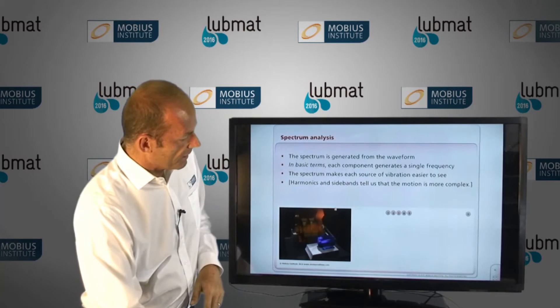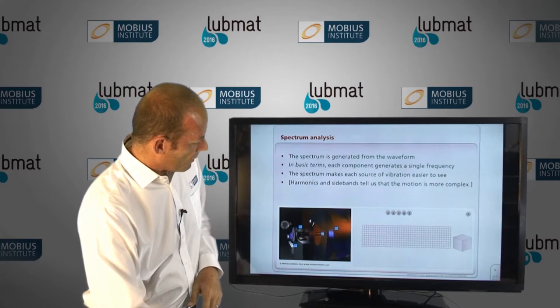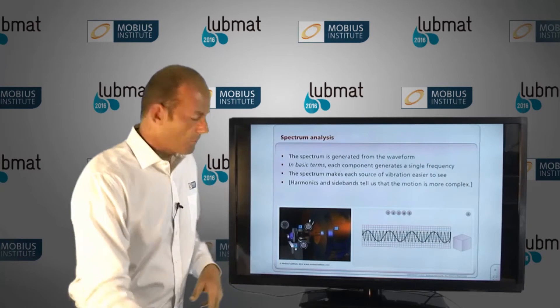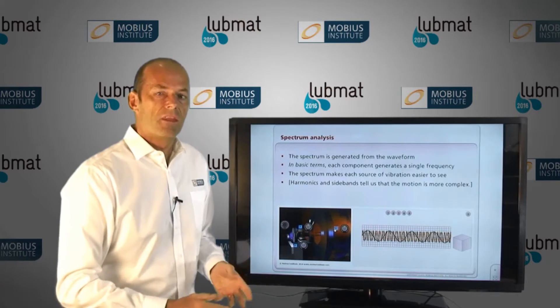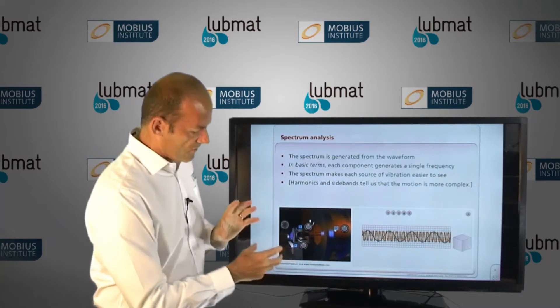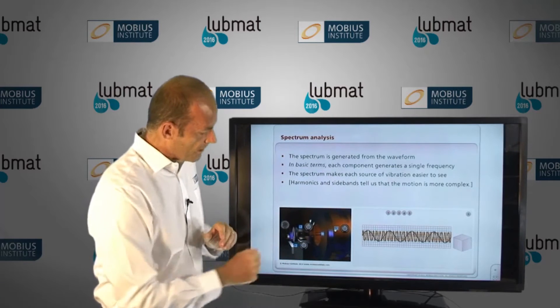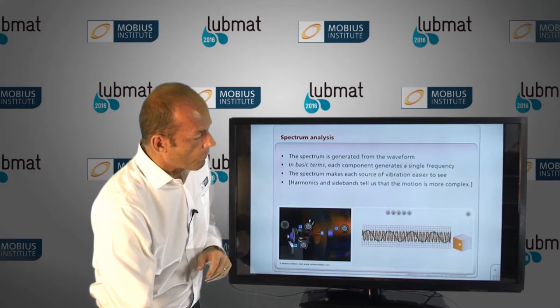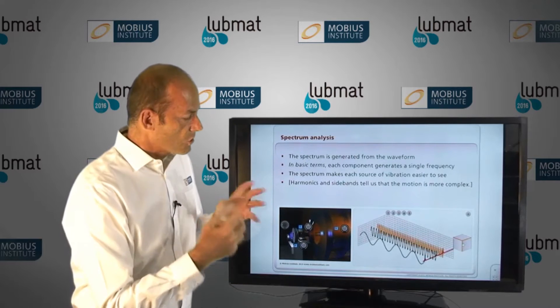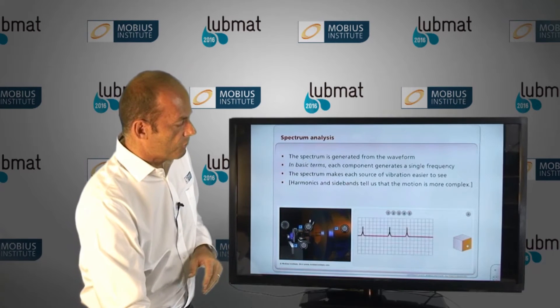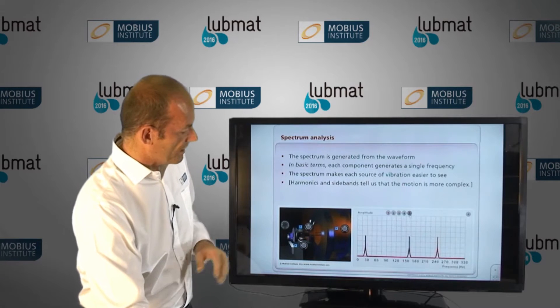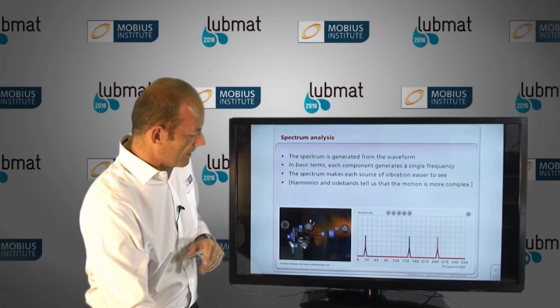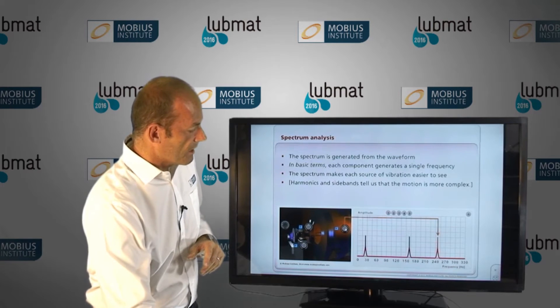One of the simulations we use lets us look at vibration from the bearings, vibration from the shaft and any unbalance that might occur there, and vibration from a fan. I've color-coded these: green from the bearing, grey from the shaft, and orange from the fan. What we want to do is split those sources of vibration up so that we end up with a spectrum — and that's where the spectrum comes from. We can therefore relate vibration from the shaft to a peak in the spectrum, from the bearing to a peak, and from the fan to a peak.